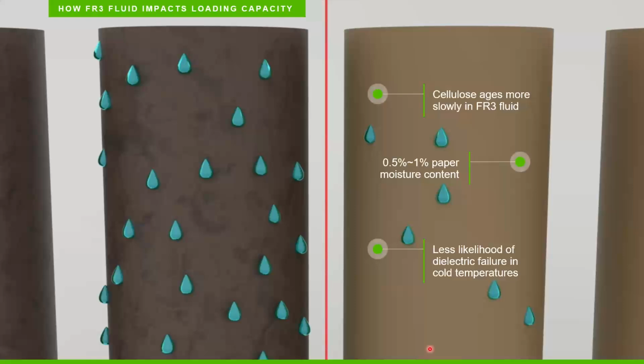On the left side, you can see a transformer filled with mineral oil that has reached the end of life. You can see how the insulation and the paper has become dark and brittle, as we saw in the pictures at the beginning. On the right side, you have the same transformer filled with FR3 that, under the same loading and circumstances, has consumed just around 12 to 15% of the lifespan of the transformer. This is because the cellulose ages more slowly in FR3 fluid, between 7 and 8 times slower.